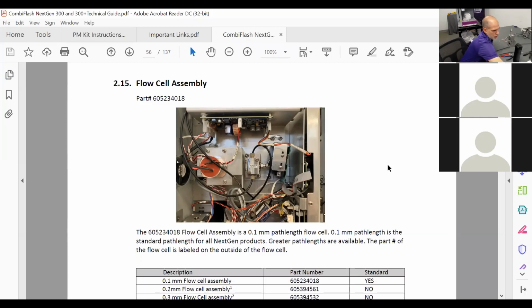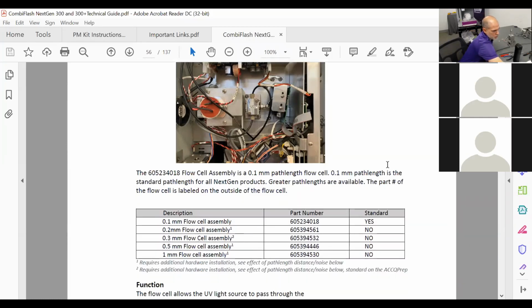So here it's talking about that, and it's talking about some of the options you have to purchase. If you change out your flow cell for a larger gap, write that down somewhere, keep that in mind, because if we do troubleshooting with you remotely and we don't know that you have a larger gap, we're just going to keep troubleshooting and we're never going to figure it out. Okay, so we need to know if you have a larger gap in your flow cell. Now, I would guess that 98% of the NextGens in the wild have the standard flow cell inside them. So keep that in mind too if you're servicing them.